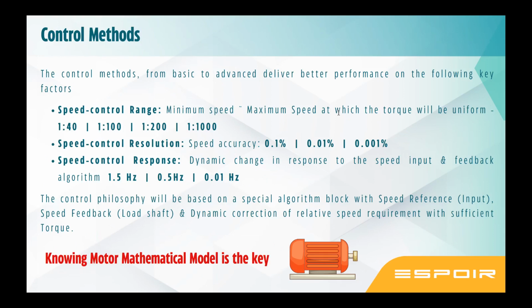Now, in an open loop vector control, you get a maximum speed range of 1:1000. Again, it is just for a reference I gave. It varies from manufacturer to manufacturer and software to software. Now, when you run at 1:1000, means 1.5 RPM, you will be able to control the motor and deliver the torque at the same time. So now you understand why selecting a particular control method is very important.